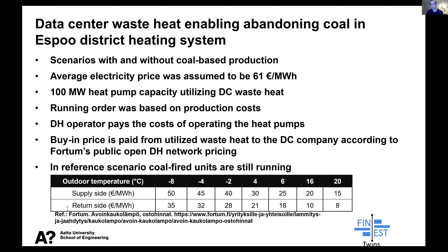According to the results, abandoning coal leads to a small increase, about 2%, in average district heating production costs. But if 100 megawatts of waste heat is added to the system, costs can be lowered to around 2% below the reference level, which is the coal system without waste heat. About 80% share of renewables in production can be reached with this data center waste heat, which corresponds well to Espoo's 2025 goal of 85%.